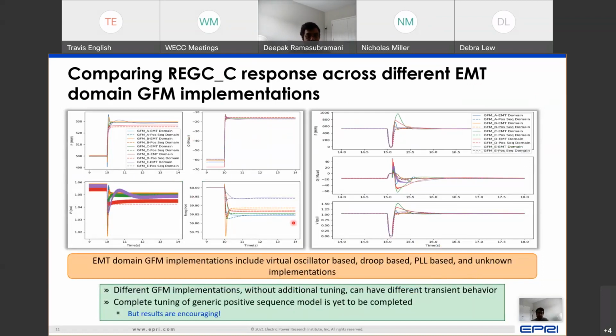in a positive sequence environment. And still more work is left to be done, of course, to complete the tuning, to make it more robust, and maybe even have more improvements to this model over and beyond what we already have. But the fact that the results are encouraging and they provide this trend of response really goes to show that we can continue to get more benefit from new positive sequence models, which is not meant to say that they can replace EMT or that you don't need to do EMT studies. What's meant to say is that it provides more tools to a planner so that they can get a more informed picture of their system and really identify where they need to do EMT studies, rather than having to do EMT studies on a whole set of contingencies, which may be computationally not very efficient.